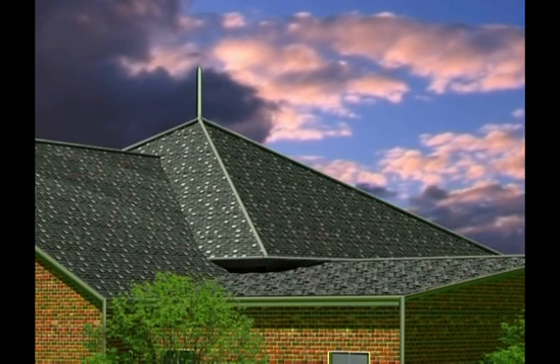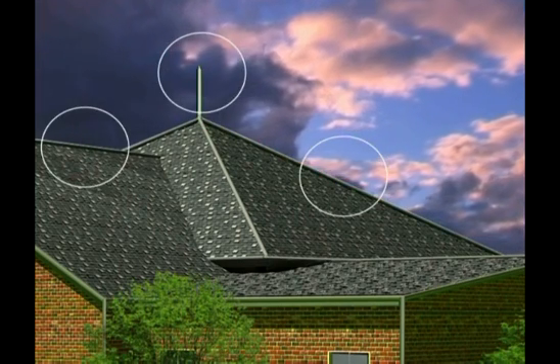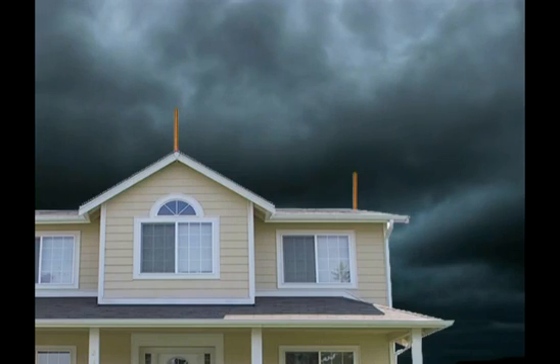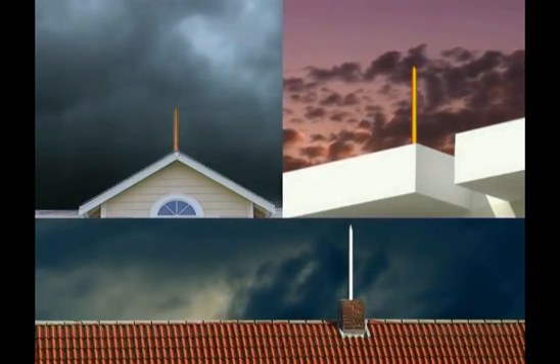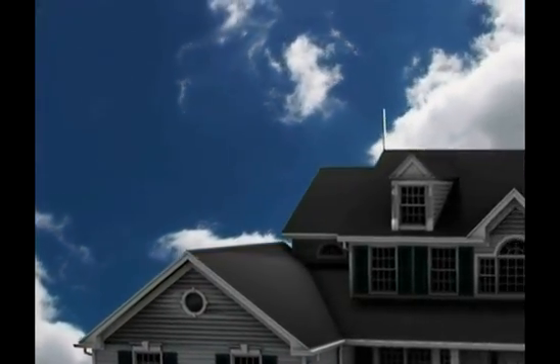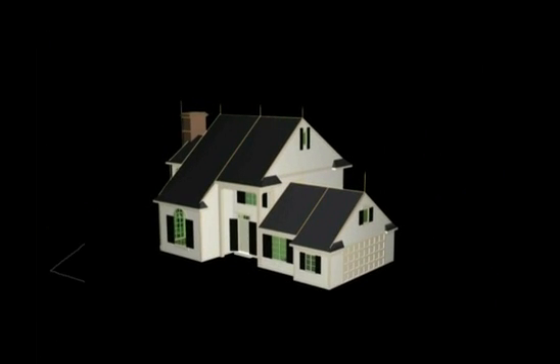The air terminal is the metallic column placed at the highest point of the building. An air terminal can be made of any conductive metallic material. Bigger building complexes need more than just one air terminal. In such buildings, more air terminals are to be fixed. These air terminals are to be linked through copper, aluminium, or GI metallic strips to the earthing system.